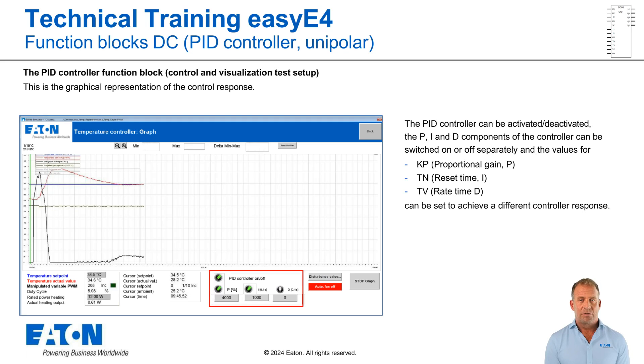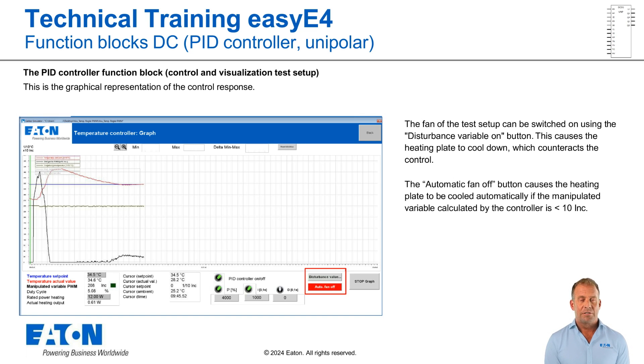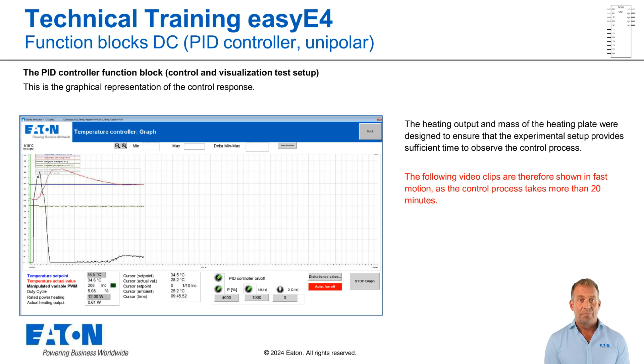To determine useful control parameters, the parameters for the P, I and D components can be set and activated or deactivated separately. KP is indicated as a percentage — the value 4000% represents a 40-fold proportional amplification. Reset and rate times are set in 0.1 second units, so a reset time of 1000 results in a time value of 100 seconds. The fan of the test setup can be switched on using the disturbance variable on button, causing the heating plate to cool down and the control mechanism to work in the opposite direction. The automatic fan off causes the heating plate to be cooled automatically if the manipulated variable calculated by the controller is lower than 10 increments. The control process takes a little more than 20 minutes in real time, which is why the following recordings are played back at several times the normal speed.